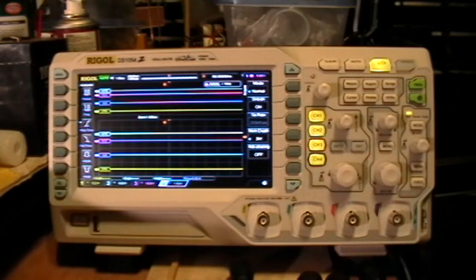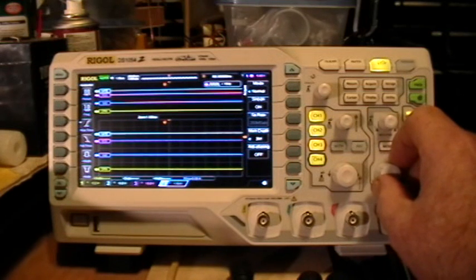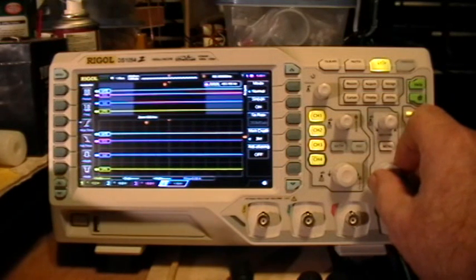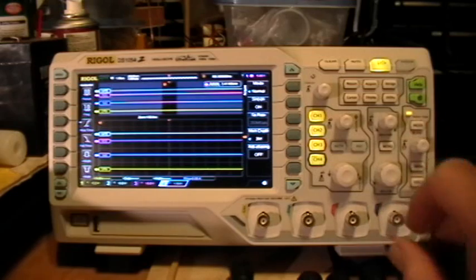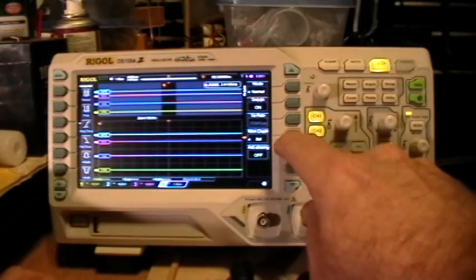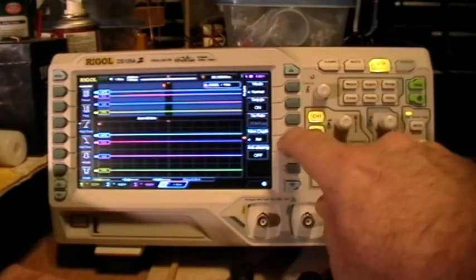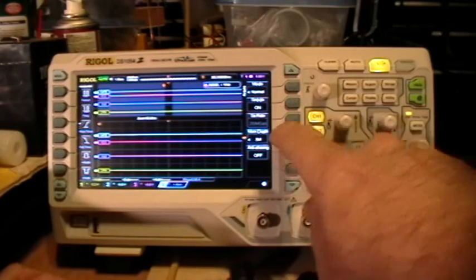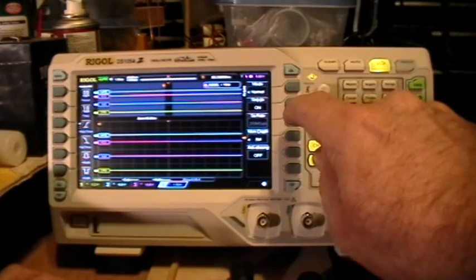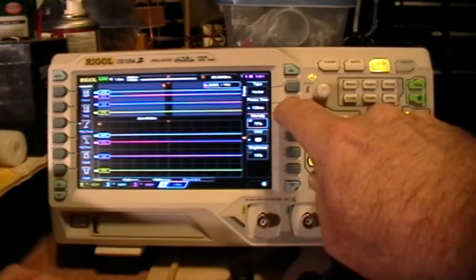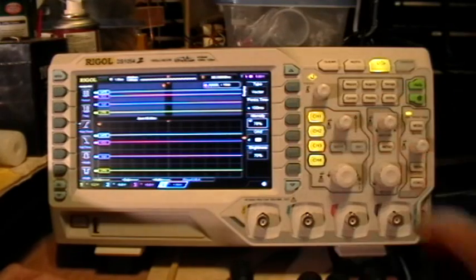But, if we are in Horizontal Zoom, and with Auto Set, or with 3 megapoint set in Memory Depth, and 100 millisecond set in Display Persistence.